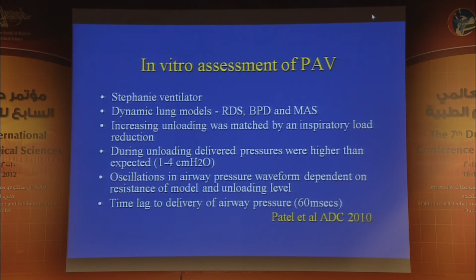Yes, when the unloading was increased, the inspiratory load was reduced. But the ventilator overshot and gave more pressure than was needed to compensate for the infant's respiratory abnormalities. And perhaps more concerning, when we were trying to compensate for the resistance of the models, if we got it wrong, the unloading was too great, then there were oscillations in the airway pressure waveform. And additionally, there was something which we used to call the trigger delay. The infant made a respiratory effort, and it took the ventilator 60 milliseconds to respond. So during that time, the baby is receiving no respiratory support, and clearly that increases the work of breathing.